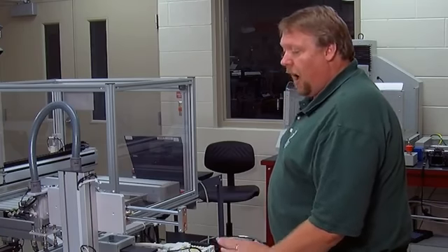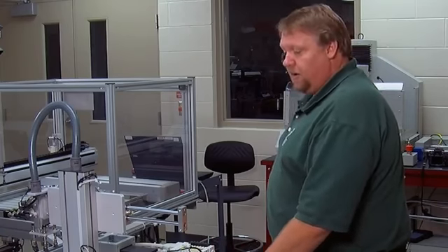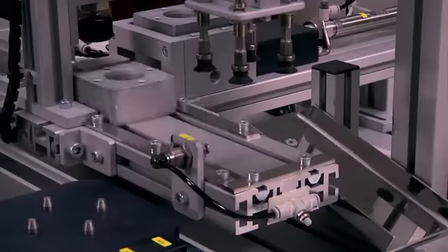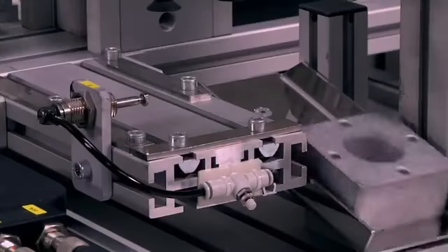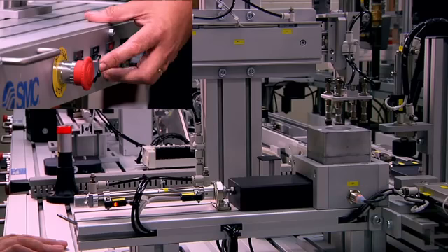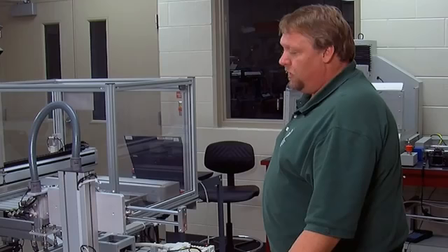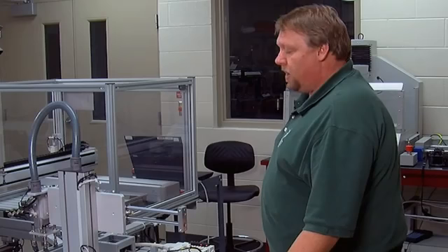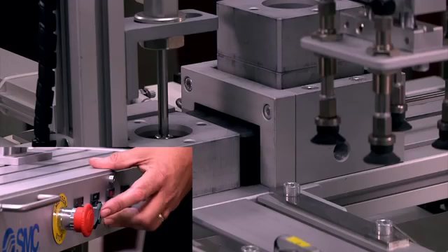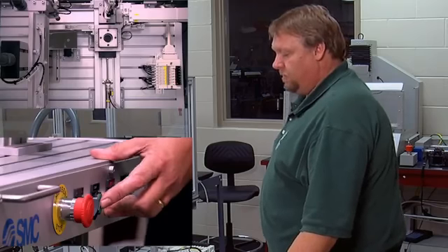So at this point we have defined our series of events, our step logic. I recommend that you use the steps that I just called out, which was 9 steps total. We'll go through one more time, a little bit faster now, just calling out each step as it occurs. Step 1 is extend the base cylinder. Step 2 is extend the inspection cylinder. Step 3 is retract the inspection cylinder. Step 4 is retract the base cylinder.